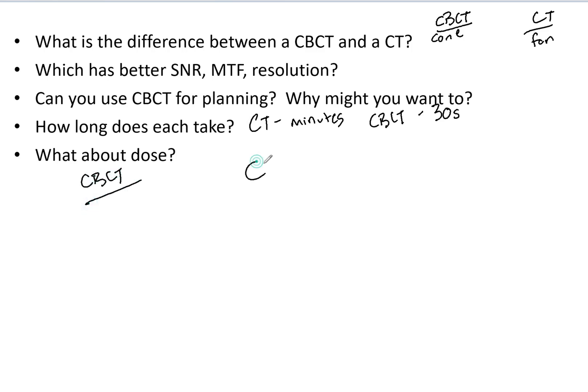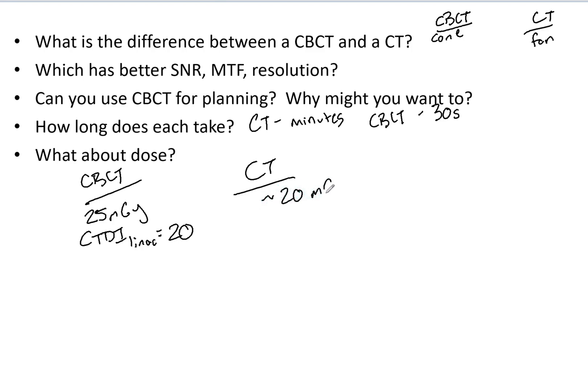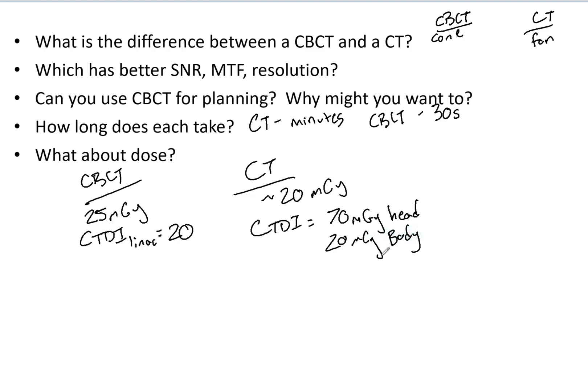For cone beam CT, the dose is around 25 mGy — for a TrueBeam linac it can be around 20 mGy. For a diagnostic CT, we're also looking at around 20 mGy, but the CTDI differs: approximately 70 mGy for the head and about 20 mGy for the body. A good question to explore on your own: why does the head have a higher CTDI than the body? It's an important concept they could definitely ask on your exam.